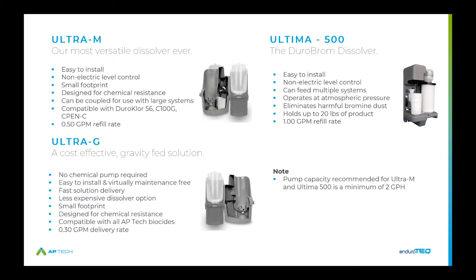The Ultra-G is an underutilized gravity dissolver — it doesn't require a chemical pump. You use gravity to allow solution to be delivered into the system. Any opportunity to utilize the Ultra-G for biocide addition — and for other chemistries like surfactants, scale and corrosion inhibitors — we feel is a no-brainer. It's ideal for applications like process waters that are below ground. It has a high delivery rate and it also accepts all of our biocides and surfactants.